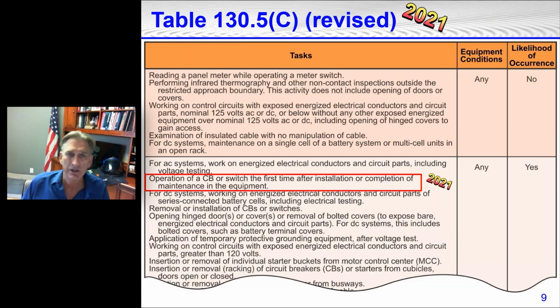All right, so let's look at some of these. This is table 130.5C. It goes, of course, beyond what I've got shown on the screen, but this is the top part of it. You've got the task on the left side, next to the far right you've got equipment conditions, and in the far right you've got likelihood of occurrence. If the likelihood of occurrence is no, then no arc rated PPE is required. If it is yes, then arc flash PPE is required.